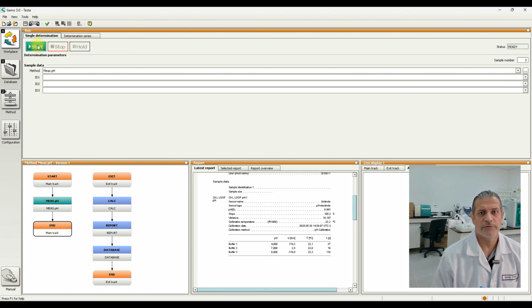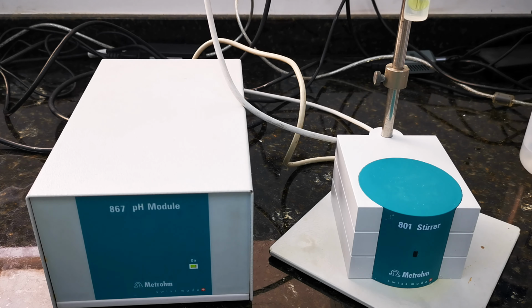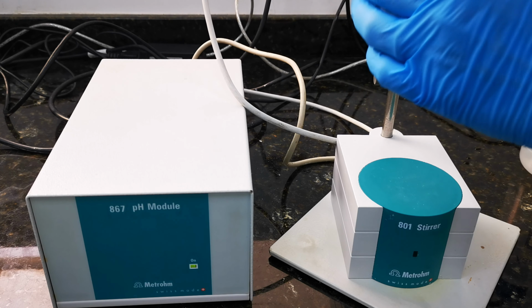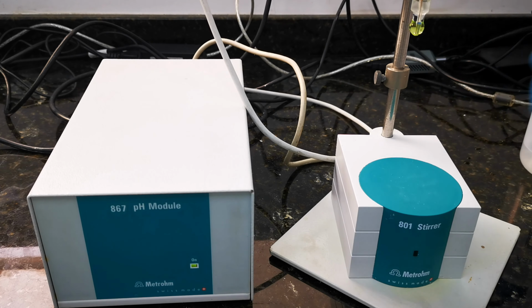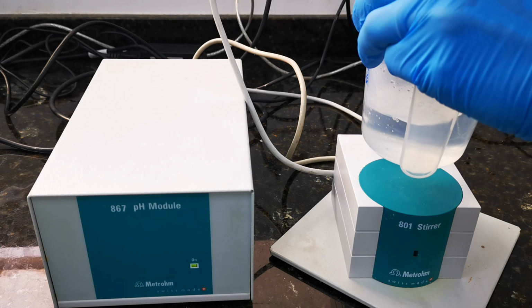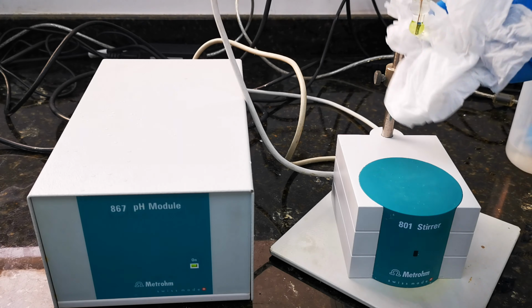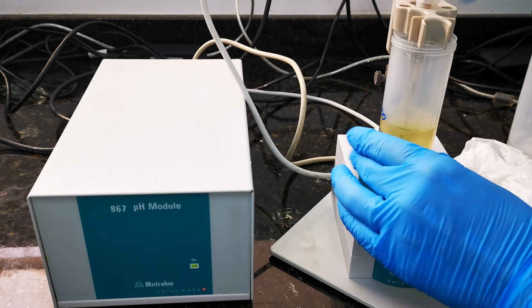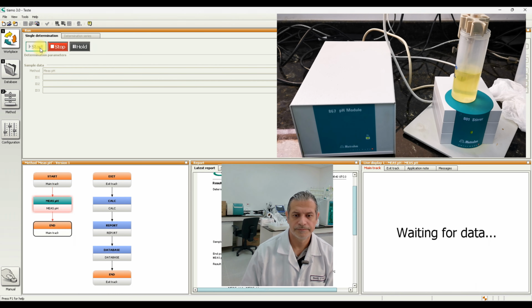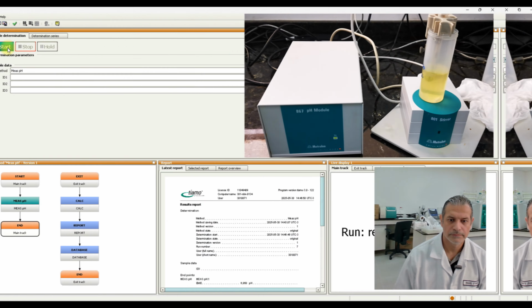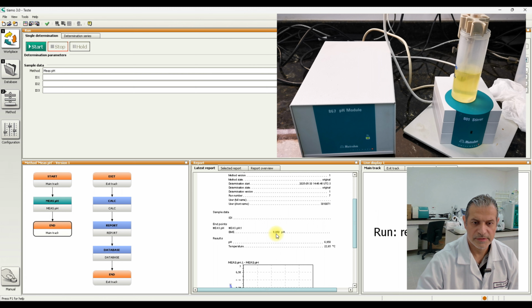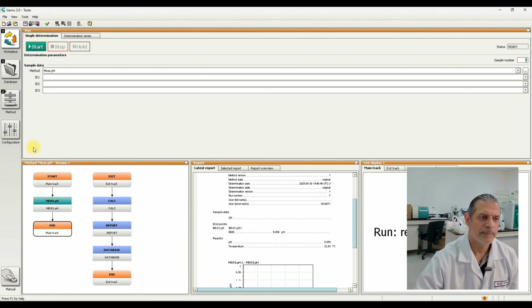If you want that the software asks you to put a sample before starting the measurement, we can add a box that is a request box. We are going to do this after the measurement of this buffer. We are going to use the 7 one. So again, we need to rinse the electrode here. Okay, let's start. Okay, very fast now. 6.95, 22 degrees Celsius. Now we can add a request button in our method.